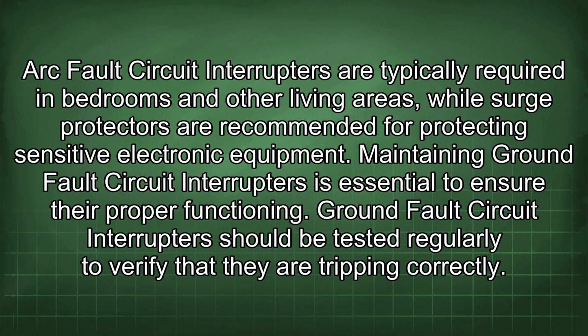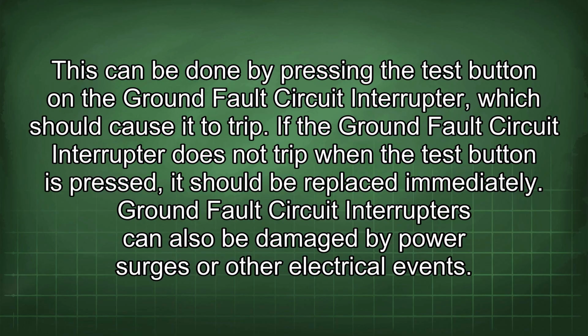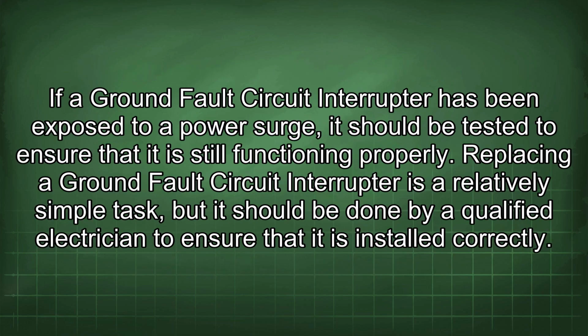Maintaining ground fault circuit interrupters is essential to ensure their proper functioning. Ground fault circuit interrupters should be tested regularly to verify that they are tripping correctly. This can be done by pressing the test button on the ground fault circuit interrupter, which should cause it to trip. If the ground fault circuit interrupter does not trip when the test button is pressed, it should be replaced immediately. Ground fault circuit interrupters can also be damaged by power surges or other electrical events. If a ground fault circuit interrupter has been exposed to a power surge, it should be tested to ensure that it is still functioning properly.